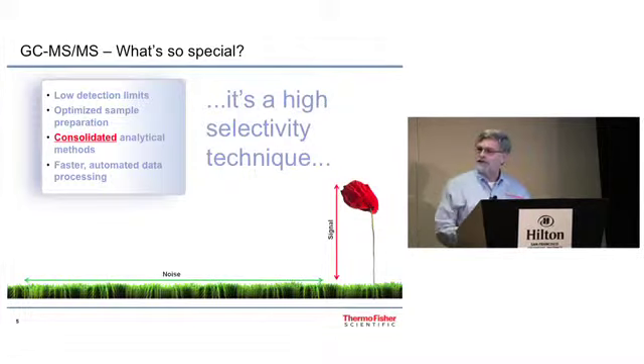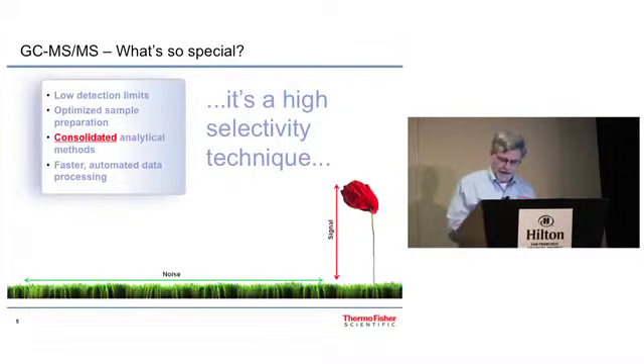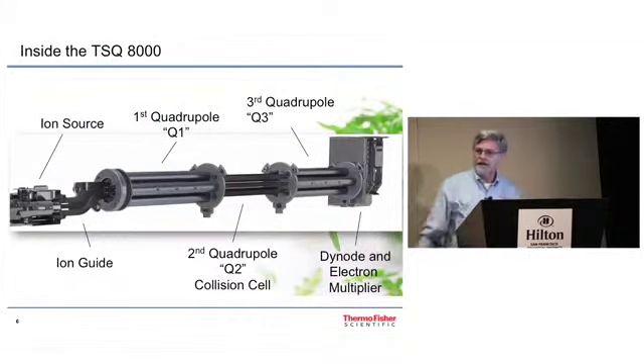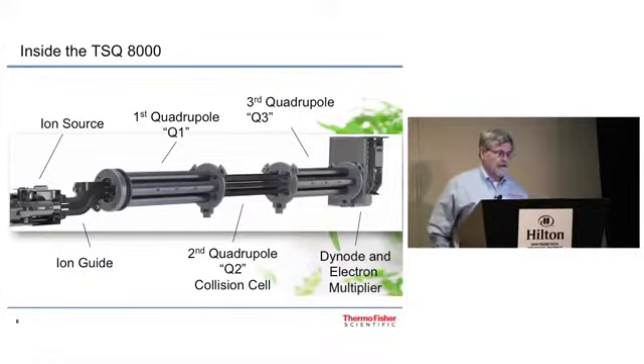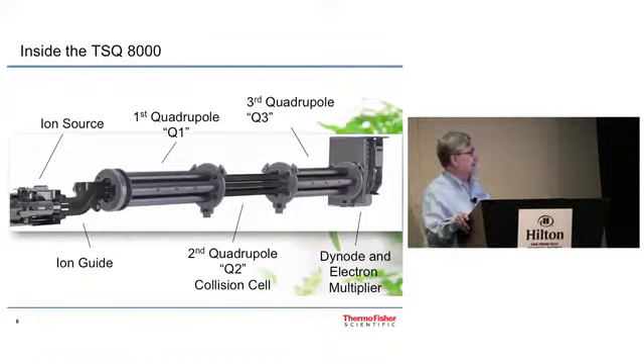And I want to just show you how a triple quad works and why it's so selective. This is what the inside of the TSQ-8000 looks like. We have an ion source, which then goes through an ion guide, which is S-shaped, goes into the first quadrupole, second quadrupole, which is the collision cell, the third quadrupole, and then into the electron multiplier.